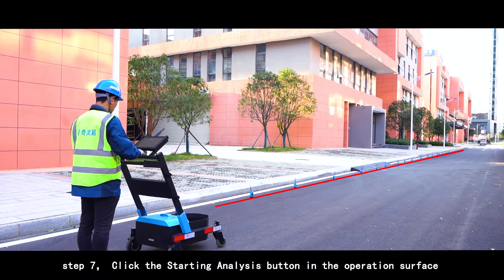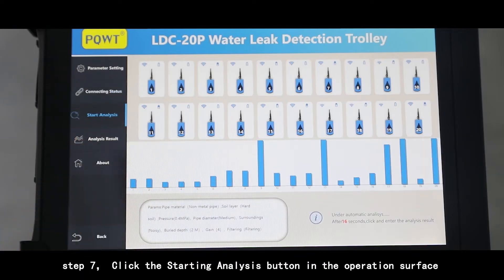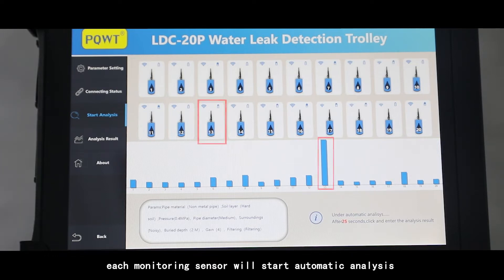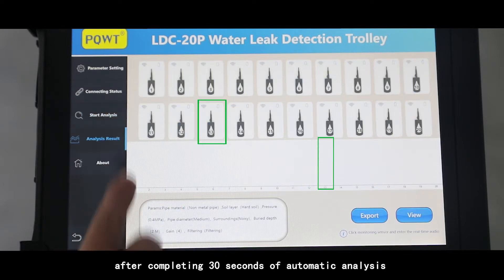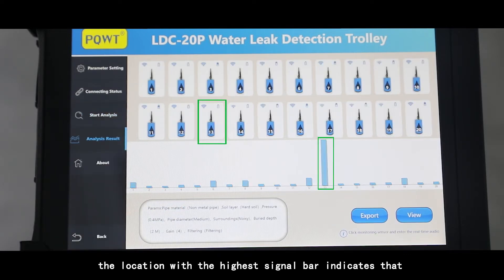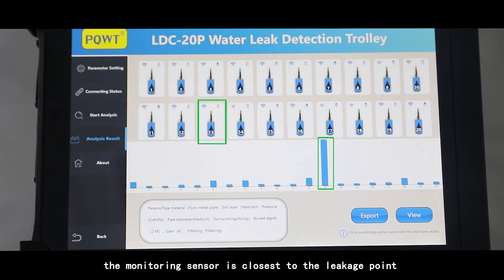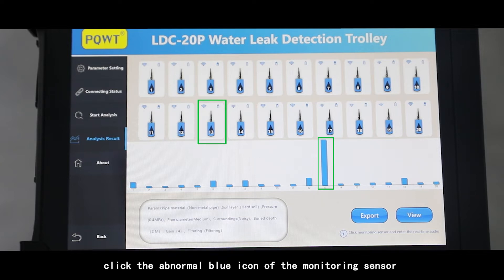Step 7: click the Starting Analysis button in the operation interface — each monitoring sensor will begin automatic analysis. Step 8: click to enter the analysis result interface. After completing 30 seconds of automatic analysis, the location with the highest signal bar indicates the monitoring sensor closest to the leakage point.